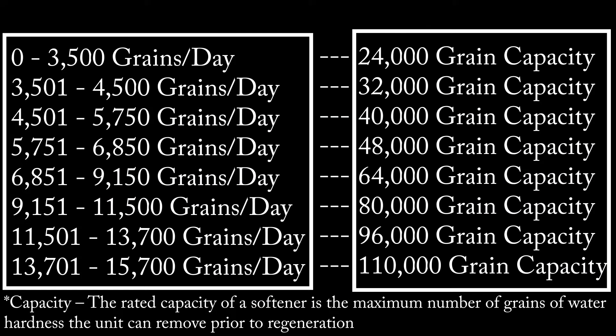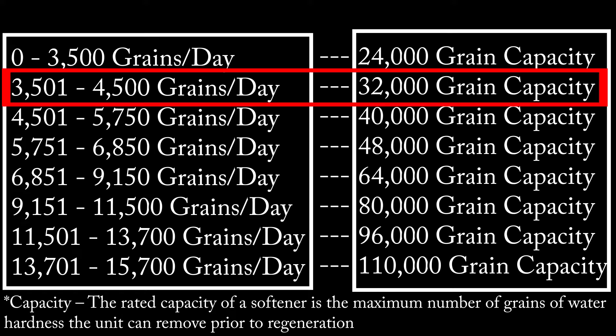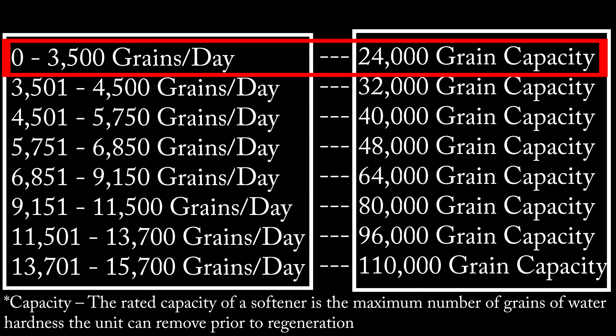Then you have to look at this chart to find out the right softener capacity. Most four-person homes use a 32,000 grain unit. I calculated 3,000 grains to be removed, therefore I need a 24,000 grain capacity water softener. The rated capacity of a softener is the maximum number of grains of water hardness the unit can remove prior to regeneration.